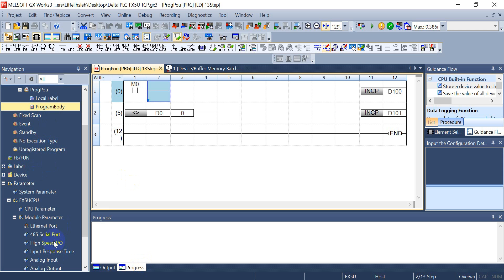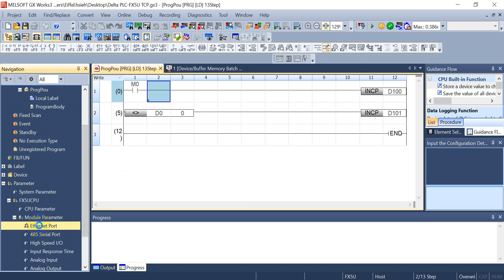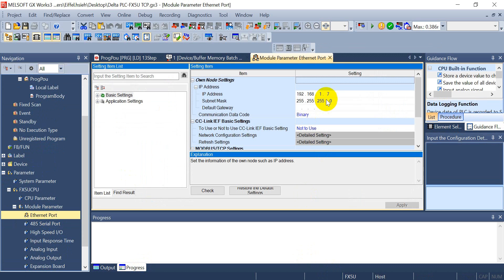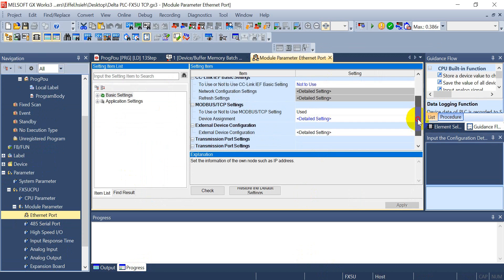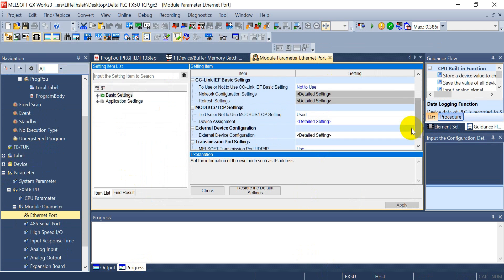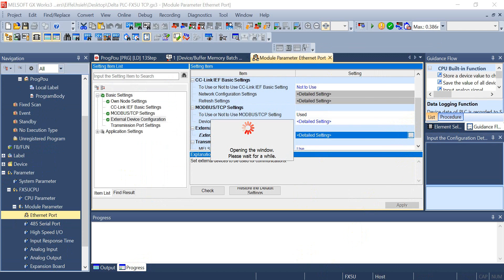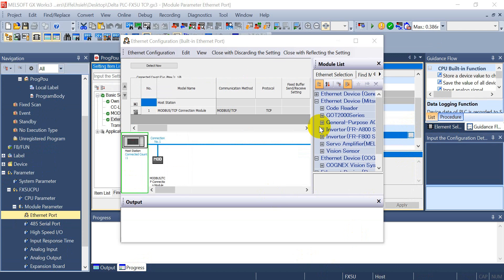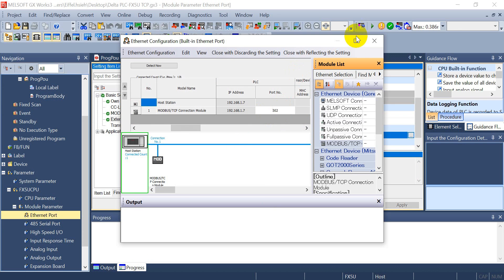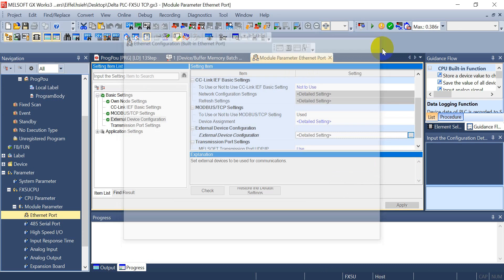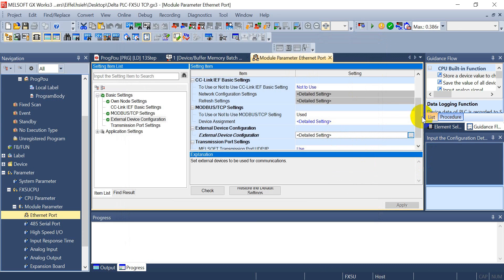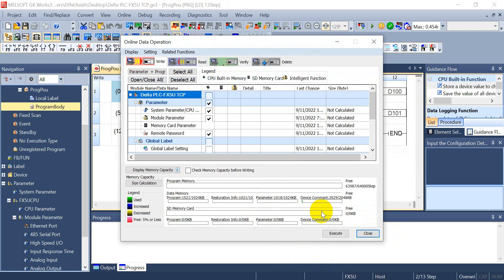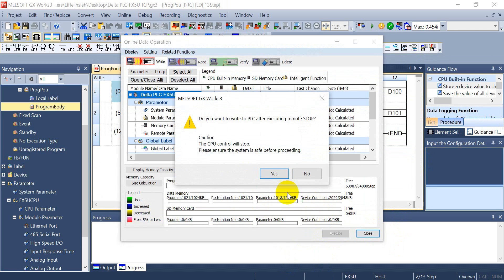Then we will switch to the software part. Here we click the Ethernet port settings, and we just find the external device configuration. Click this one and add down the Modbus TCP from here. Define the port to 502. Remember if you set this the first time, please remember to click apply. Now we can download the settings to Mitsubishi PLC.